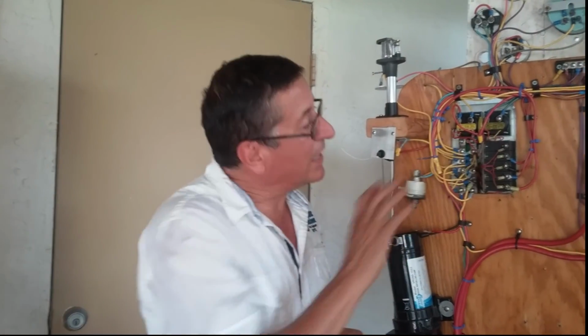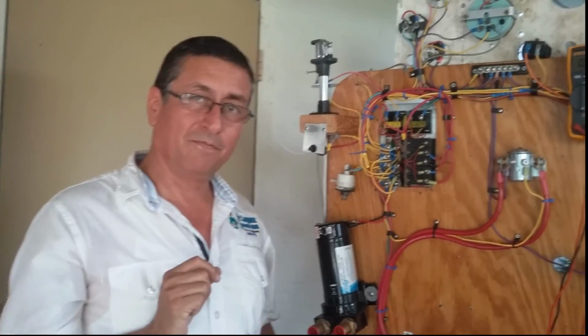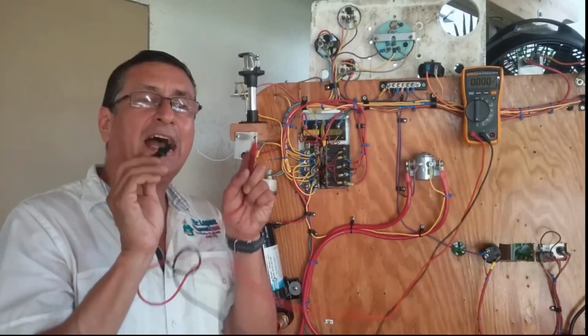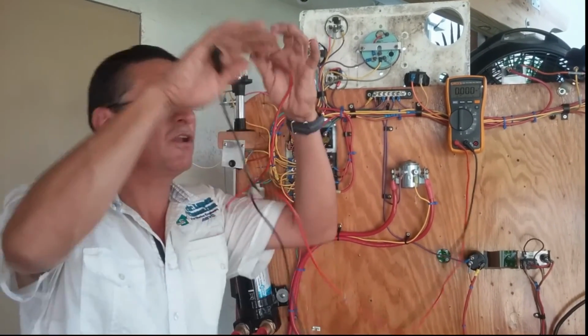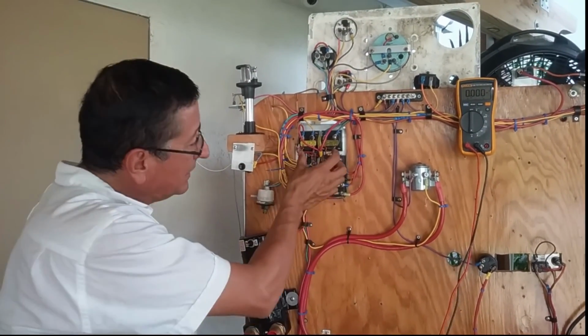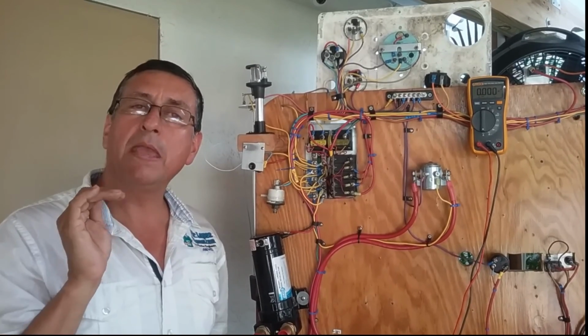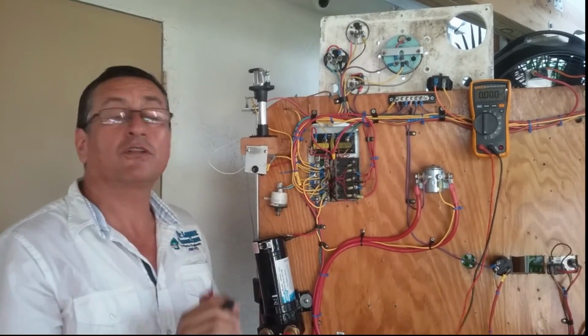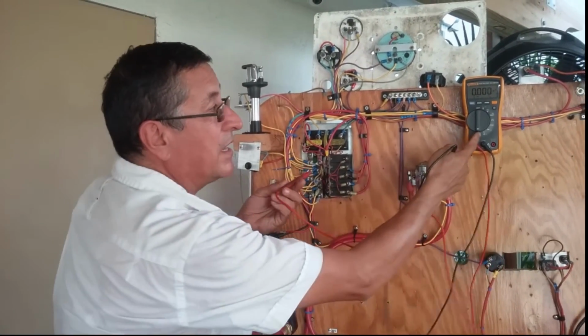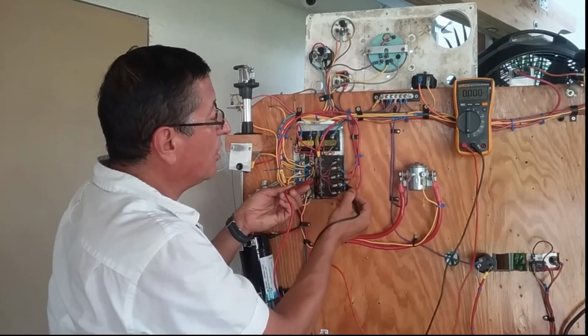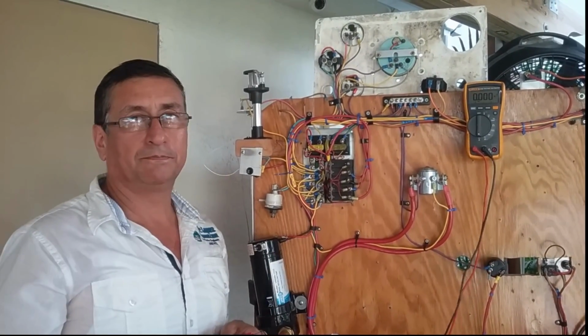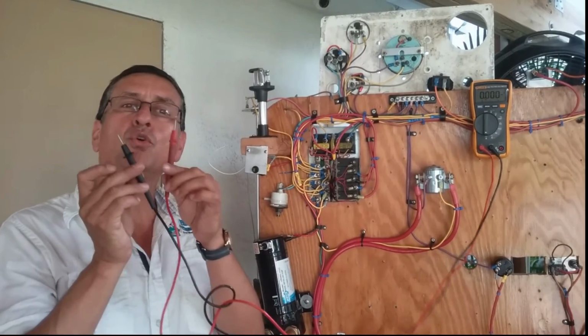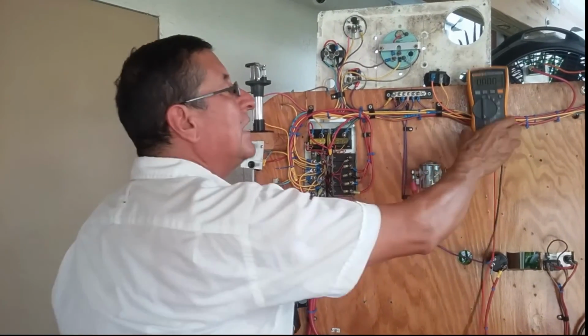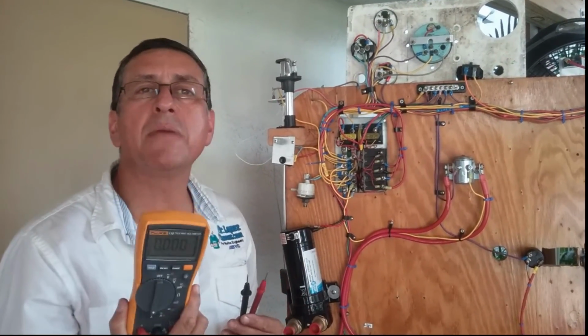In this particular example, I don't have a main breaker. When I have a main breaker, I check in that breaker the consumption of all the system. In this particular panel, I don't have a main breaker. I have individual breakers. For that reason, I can check with my ammeter the consumption of each individual equipment. That's the procedure to use the ammeter. To use an external ammeter.